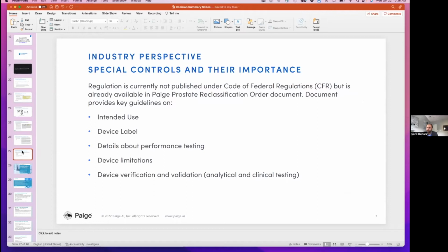So Peter did go over this overview, so I'm not going to go into the detail, but one thing that is not necessarily directly in the decision summaries, but is the next link as part of the de novo approval, is the reclassification orders. They do include the special controls until the regulation is publicly posted in the Code of Federal Regulations database. What that means is that when FDA does establish a new product classification, that classification comes with very unique special controls that each predicate manufacturer needs to review and adhere to. So it provides very important guidance. Again, it's not part of the decision summaries, but should definitely be looked at for the intended use, what the specific intended use statement includes, right?